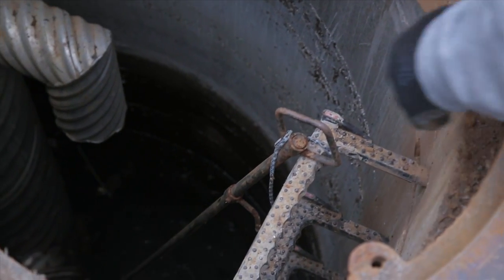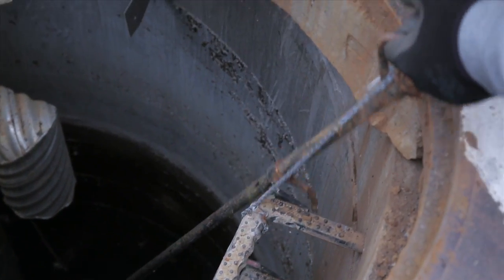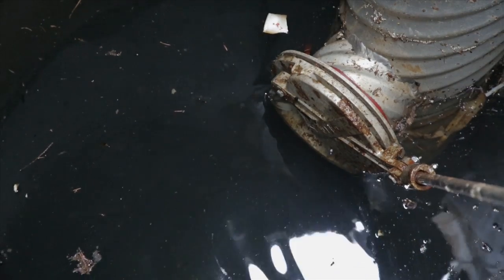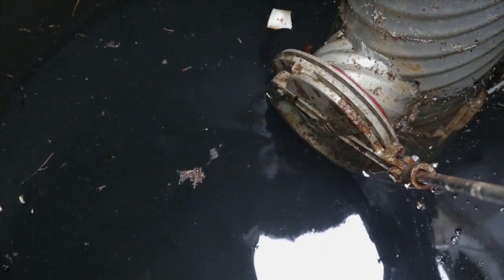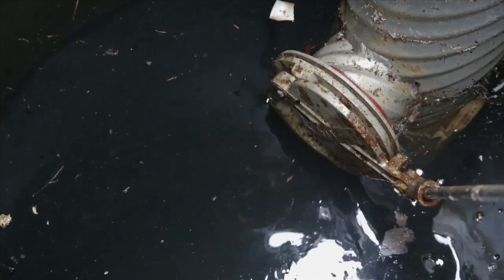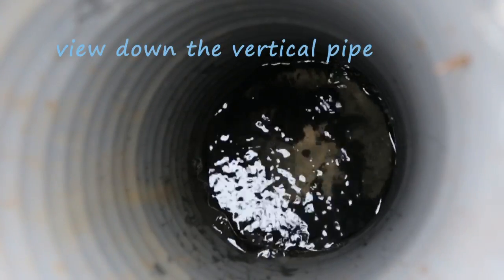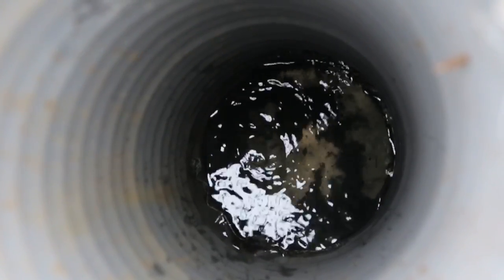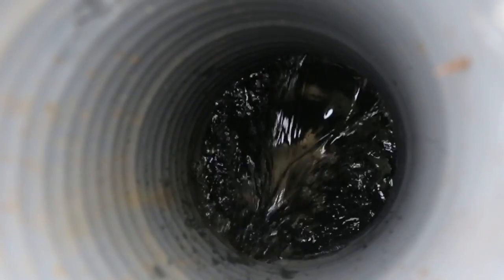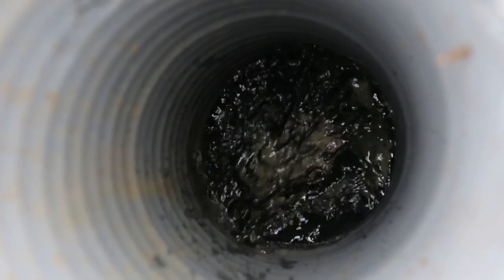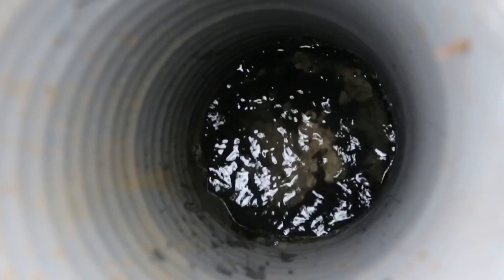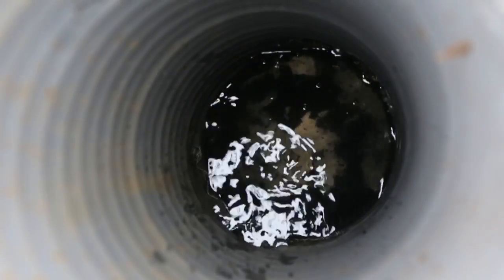Many control structures are designed with a shear gate that can be opened or closed from above. The purpose of the shear gate is cleaning and maintenance. If something is blocking water flow, opening the shear gate will allow a quick release of water, hopefully dislodging the blockage. The shear gate also allows access to the vertical pipe when needed.